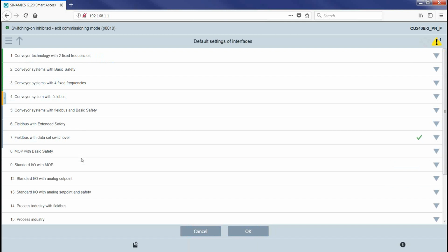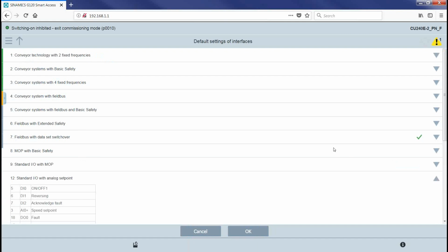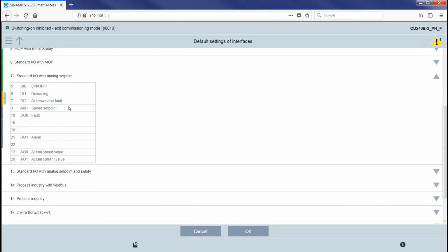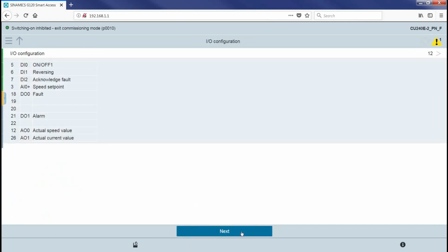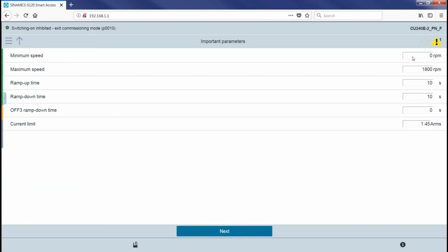IO configuration, again, I'm going to go to 12. If you click the arrow to the right, it kind of gives you some highlights of what that is going to be set to. So I'm going to select 12, see the check mark, say OK. Next. So minimum speed, max speed, I'm just going to leave it 0 and 1800. Ramp up time, if I want to change it here to 5 seconds. Ramp down time, 5 seconds. I'm going to reduce my current a little bit, 1.2, because it can cause some issues with my demo just because I don't have a very good voltage source, honestly.